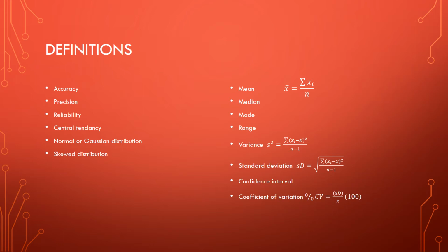And the accuracy and the precision of a particular test has to be something that you document. You don't just rely on the manufacturer's information. You have to demonstrate that you're performing the test close to or spot on for the accuracy and the precision that the manufacturer is reporting.